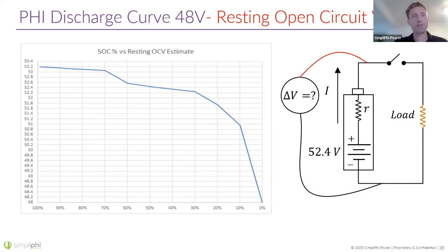As the battery is discharged, now this is not a discharge curve, so as the battery is discharged, I stop, let the battery rest, and then monitor its voltage again. Once I get down to 50%, you can see that I will be at 52.4 volts. When I go farther down, right, I get to about 52.2, it looks like on this curve. This is, again, for a resting battery, I'm at 30% state of charge.